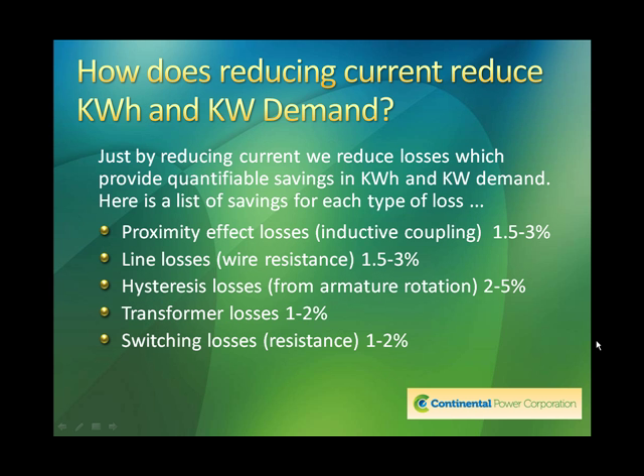If we take a look at those small savings, just by reducing current, we reduce losses, which provide quantifiable savings in kilowatt hours and reductions in kW demand. And here's a list of savings for each type of loss. Proximity effect losses. This is from inductive coupling. These are for those that are electrical engineers. You've, I'm sure, gone through this before. Even electricians know about these terms. If you don't, not to worry. But there are a number of electrical concepts here that this plays into. So if you have two wires in close proximity, there's inductive coupling, 1.5 to 3% losses from that. Line losses. This is due to resistance.